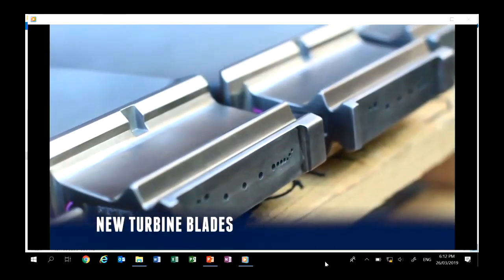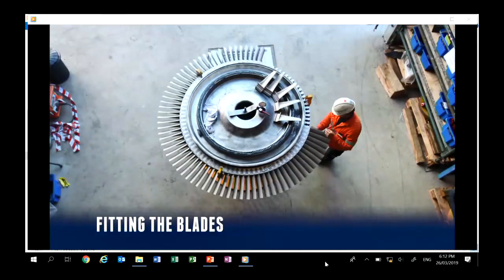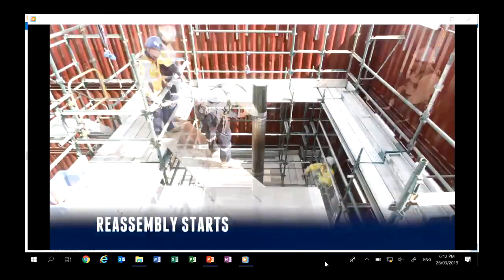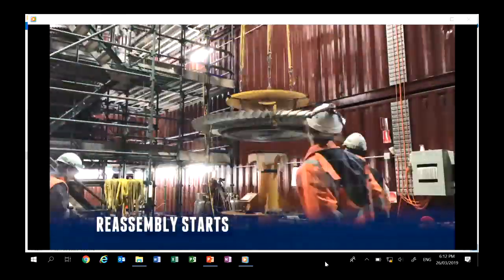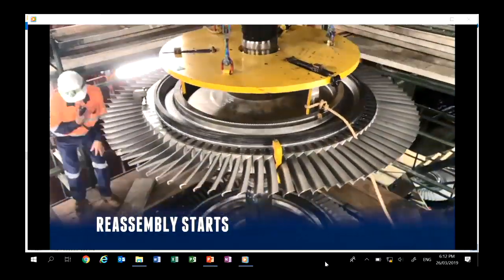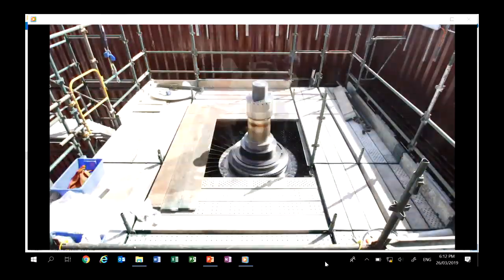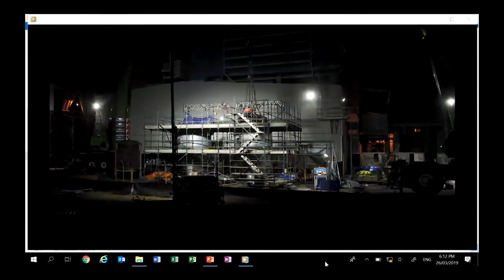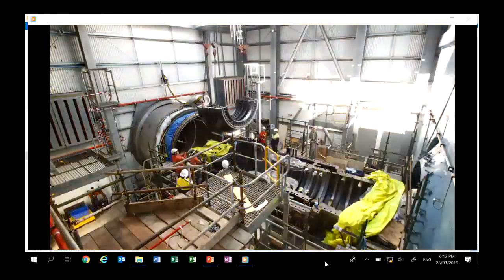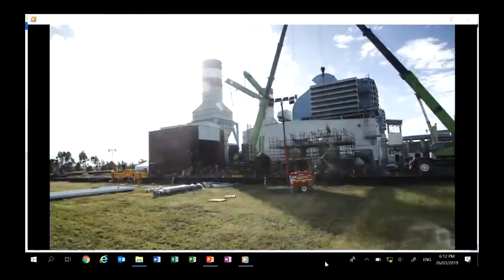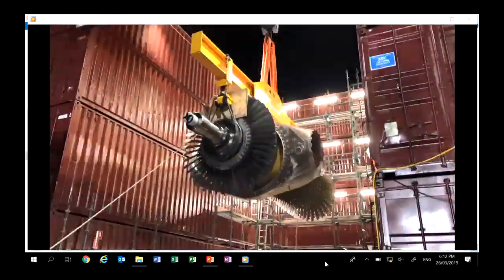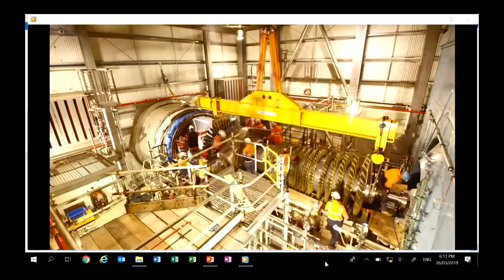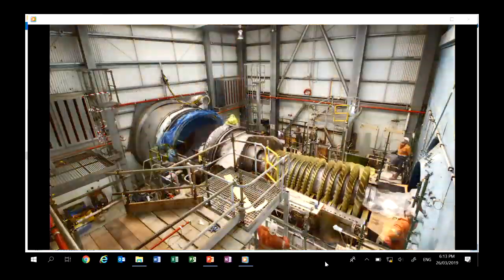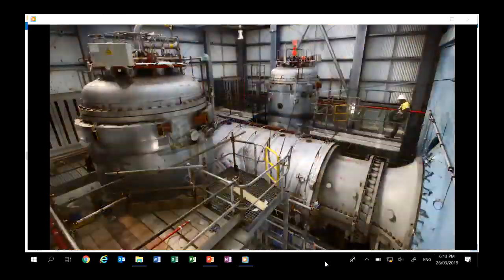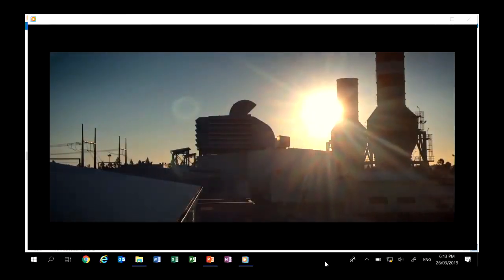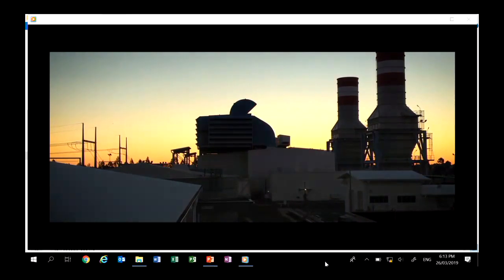So this thing is like a 300-ton Swiss watch. It comes apart into thousands of components. They all need to be tracked. Here we're replacing the blades and then restacking the rotor. So there's the rotor completely rebuilt, going back into the gas turbine. Okay, combustion chambers go back. And it's all back together again.